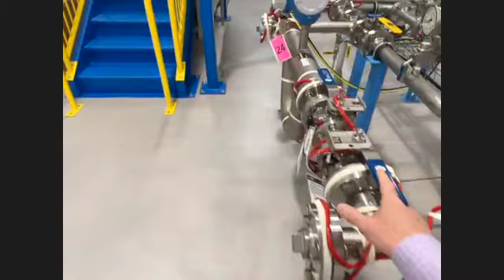So we get common questions in that a customer will call and say, oh, I have 1,000 feet of pipe, so I need about 1,000 feet of heat trace. A typical ratio would be about 30 to 40% more cable than the straight length of pipe. Typical, sometimes more, sometimes less, depending on the configuration of the piping. But in summary here, you can see we have the cable strapped on, end seal over here, power connection kit. This is a nice short little heat trace circuit that we use.